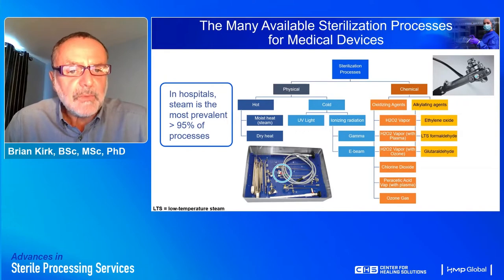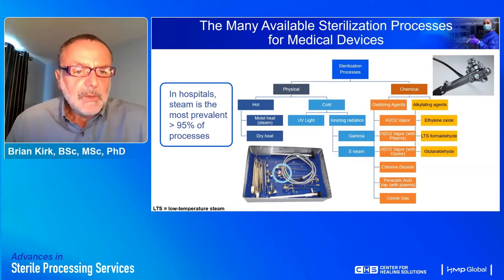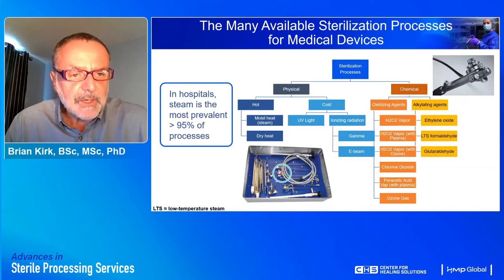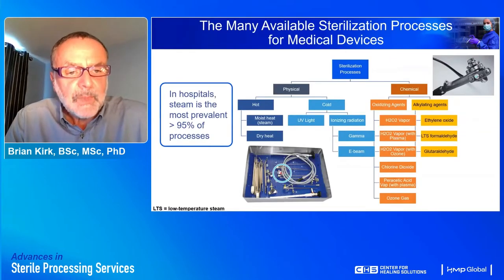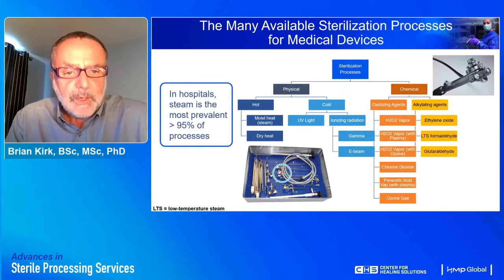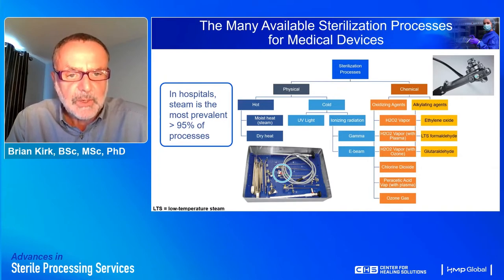On the left-hand side we have physical processes, divided into hot and cold processes. The hot processes include moist heat — steam sterilization — and dry heat. Moist heat sterilization is very familiar to hospital practitioners; probably 95% of processes are carried out using it. The cold processes include UV light and ionizing radiations such as gamma and E-beam, which are used extensively in manufacturing, less so in hospitals.